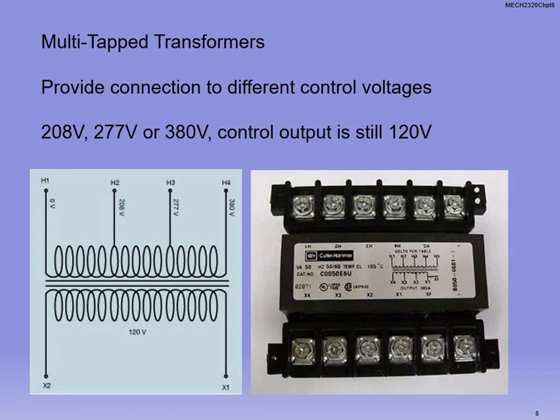So we have multi-tap transformers, okay? And these are fairly common, all right? And you'll see one of these in the lab. So based on how we make our specific connections, that's going to get us our output for 120. So regardless on this transformer, our output's always going to be 120. Do you see that? The way this would be set up, X1 and X2, always 120.